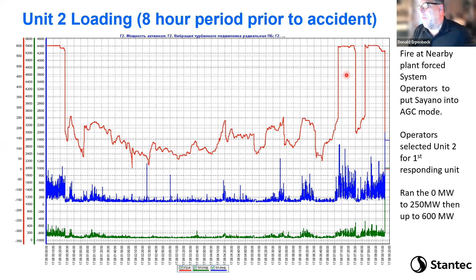Okay. And then here's what you see. This is starting at midnight. What you see is they were at 600 megawatts. They dropped down, and they basically ran in AGC mode between 250 megawatts down to 50 megawatts all night long, in this lower operating regime. For this type of turbine, we don't normally run here. It can be done, but this is not normal. We can usually find a smooth place or two down here to run, but not to go all over this full range like they did. And then they ramped up in the morning, ran up to 600, dropped back through, came back up, and then came back down in the failure.